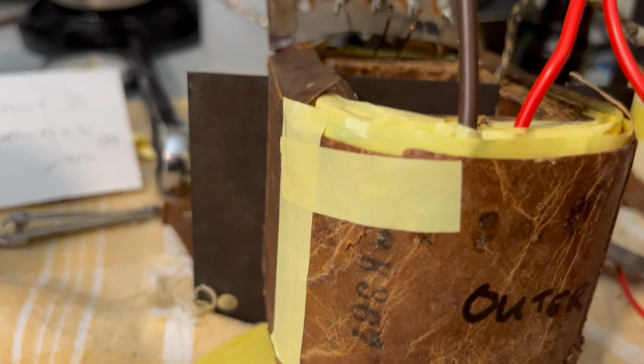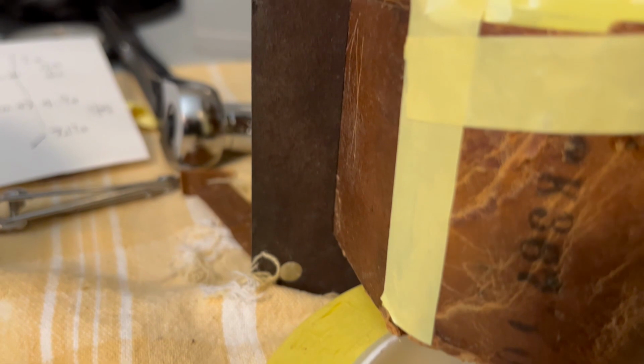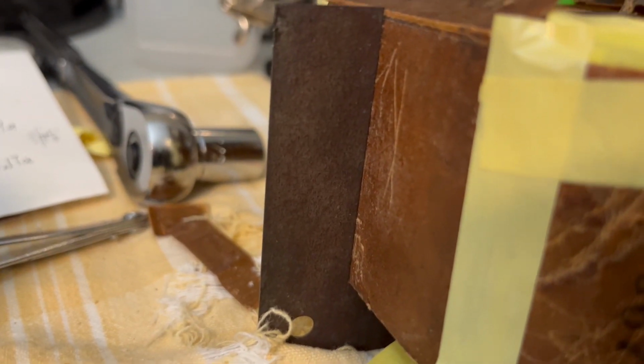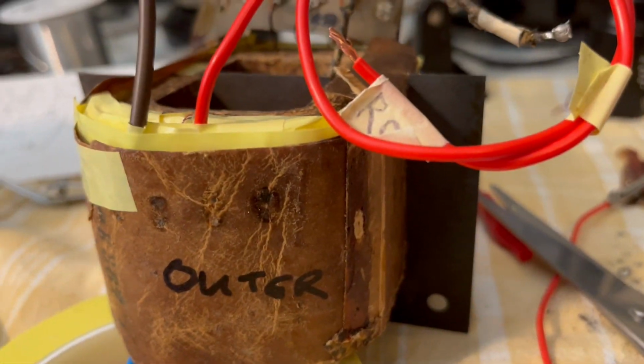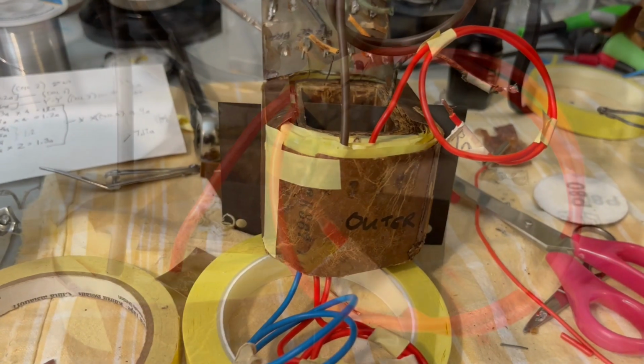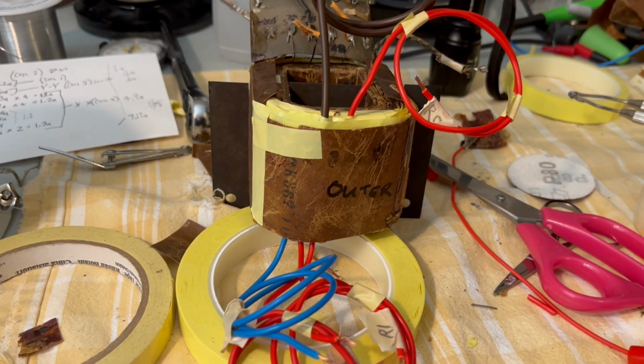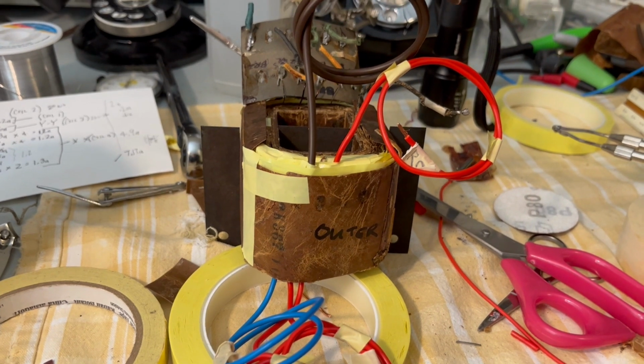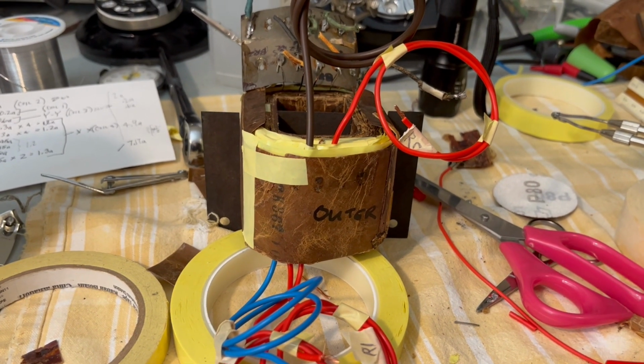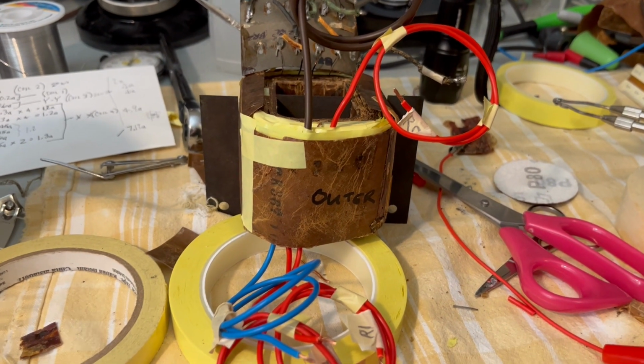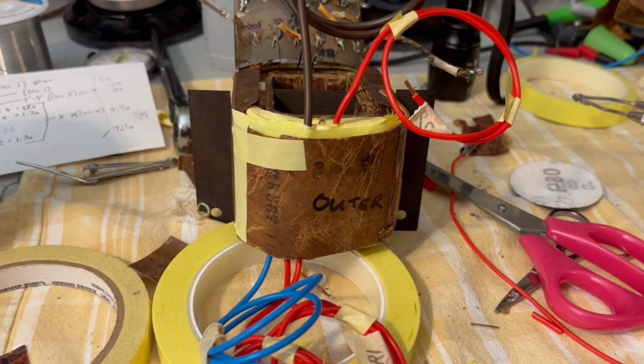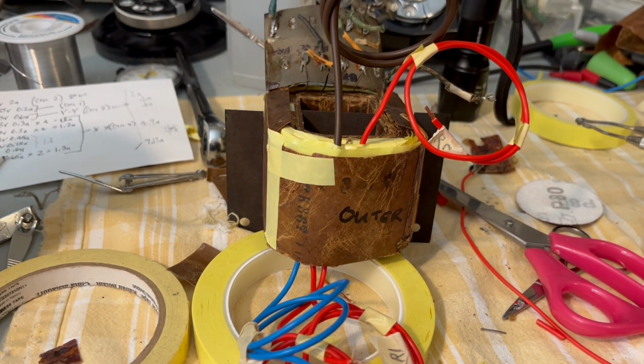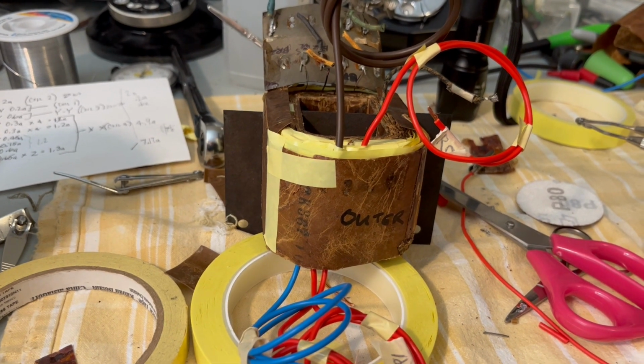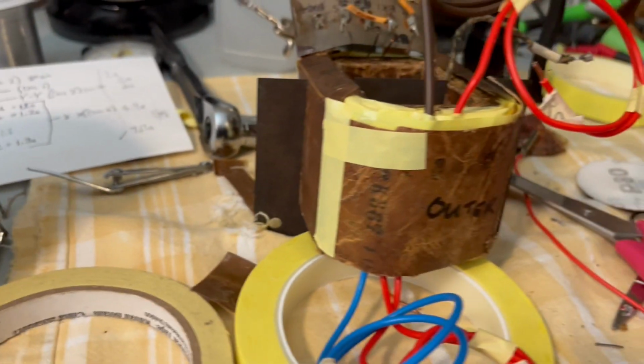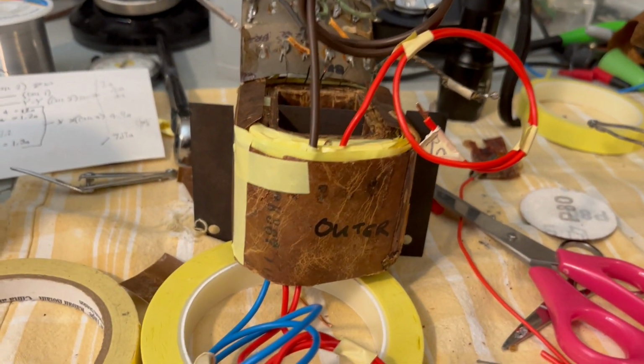It's tight. You can see the outer edge of the laminate there is right up against the paper. In fact, it's scraping the paper, cutting into it a little bit. So basically, I've done about the best I can to make sure that everything is pretty well insulated in there, and I've tested the high voltage coil end to end. It's good. I've got a couple of others that I want to go through and check, because I don't want to get any further in this. It's not that much to tear this off if I've got to go in there and fix something, but I need to buzz out the rest of those coils. I haven't done that yet.